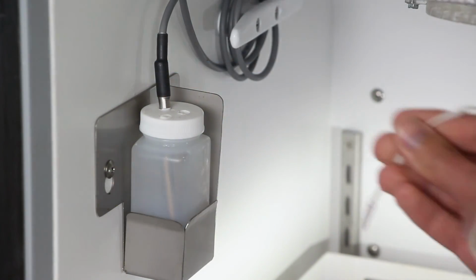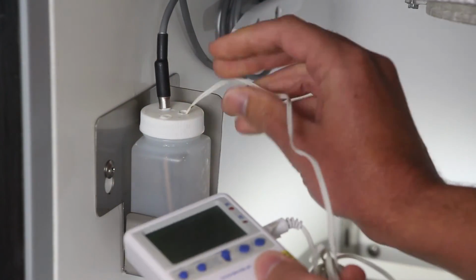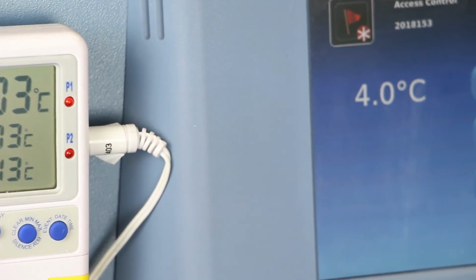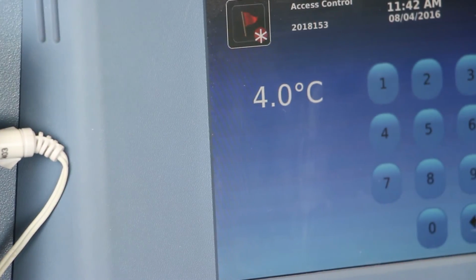Then check the calibration of the temperature display using a calibrated reference thermometer. Verify the thermometer reading corresponds with the temperature reading shown on the display.